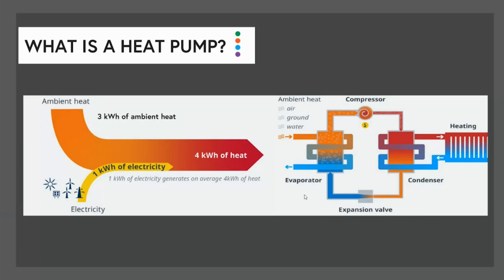Now, the condenser could be all sorts of things, but it's basically a heat exchanger that delivers energy to a system. And that could be a tank of water, it could be a heating system, which it shows in this case. So in this diagram, we're talking about the entire heat pump is this entire system, and just on the outside you've got connections that are leading out to what looks like a radiator essentially. So we're sending hot water out and we're getting cold water back. So that heat exchanger or the condenser is giving up its heat to the system, and as it does that, the superheated vapor condenses back into a liquid.